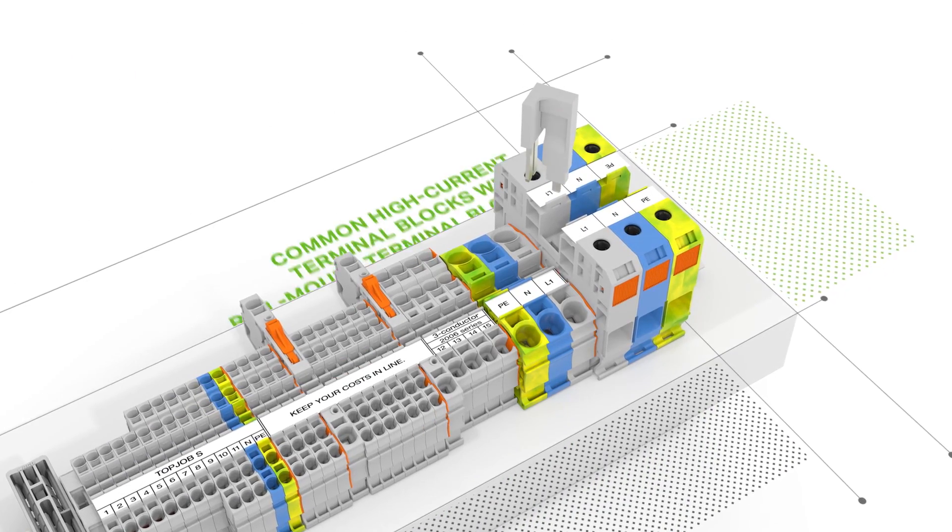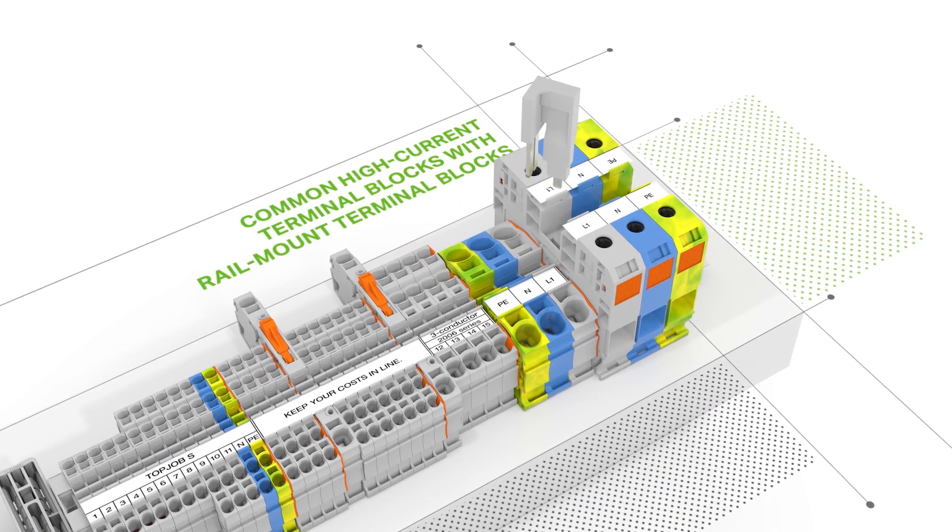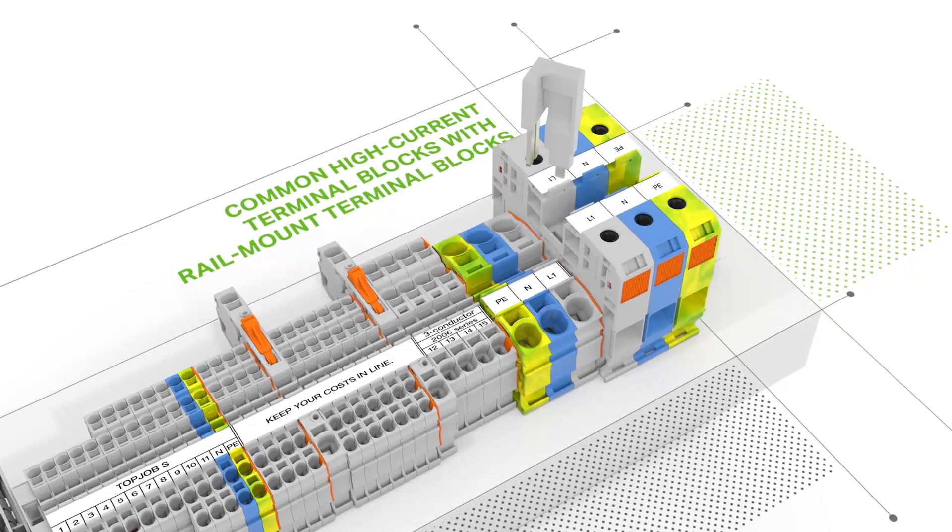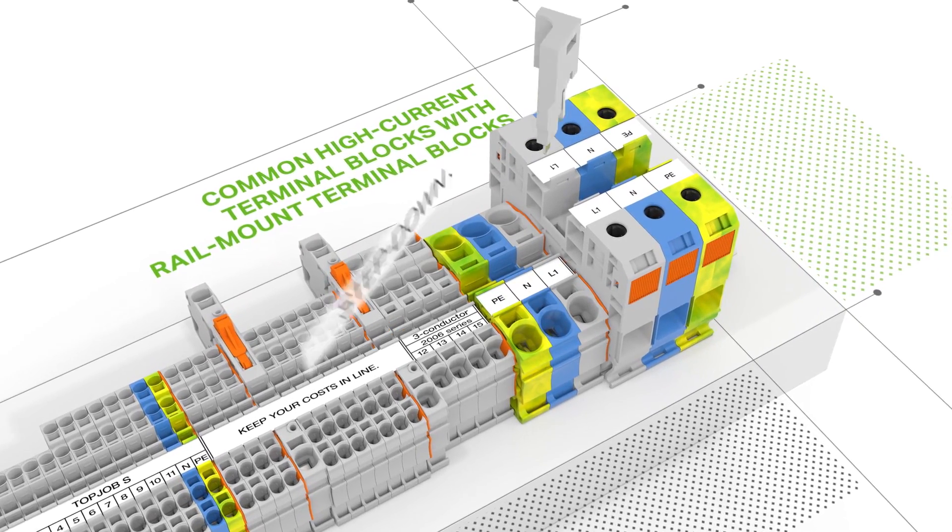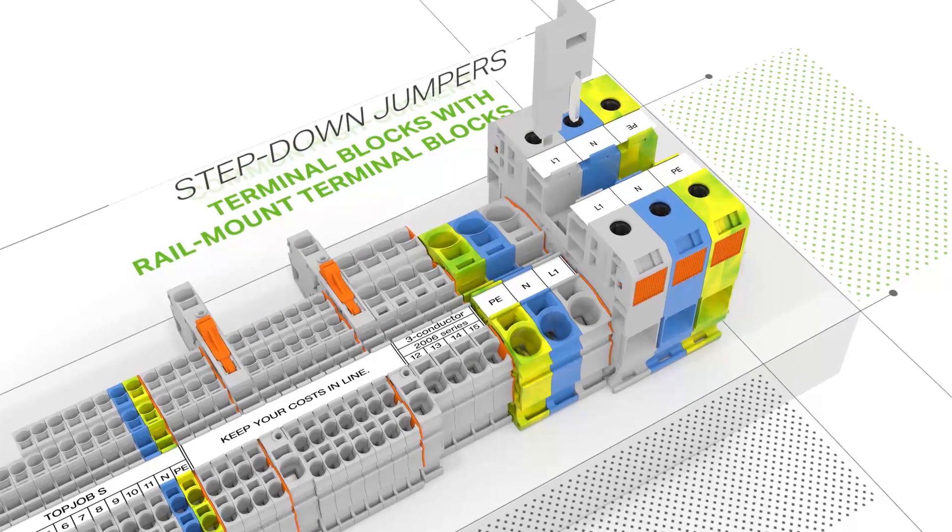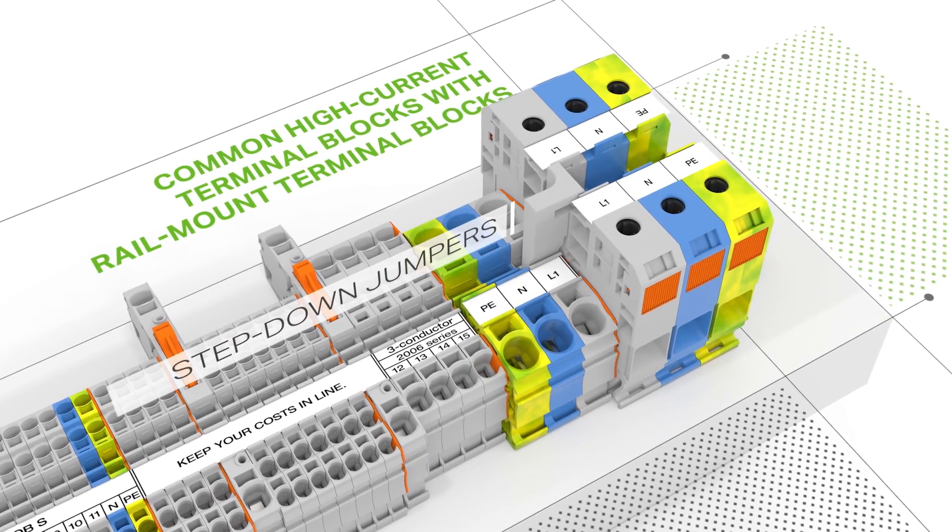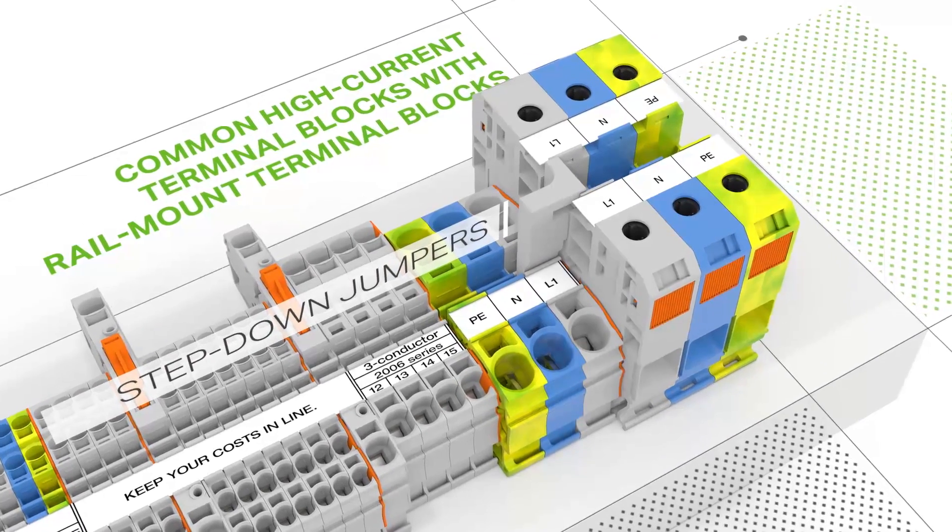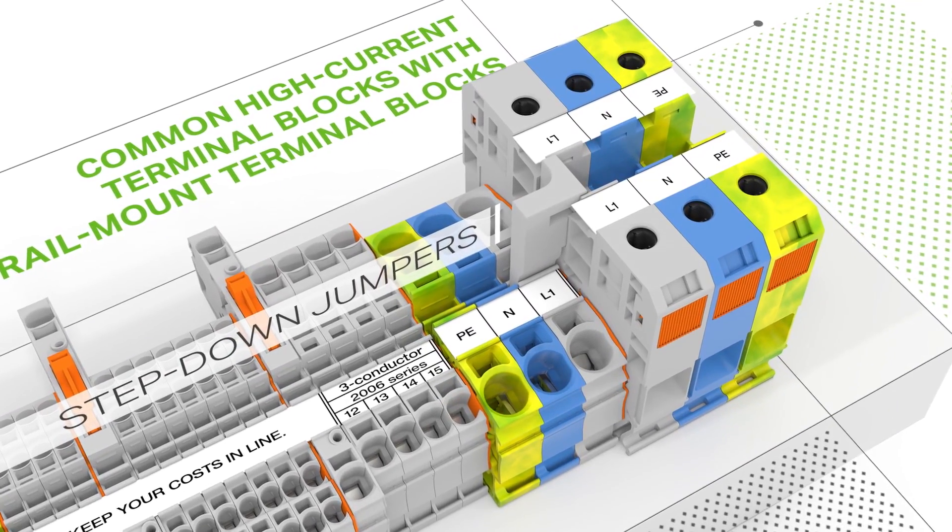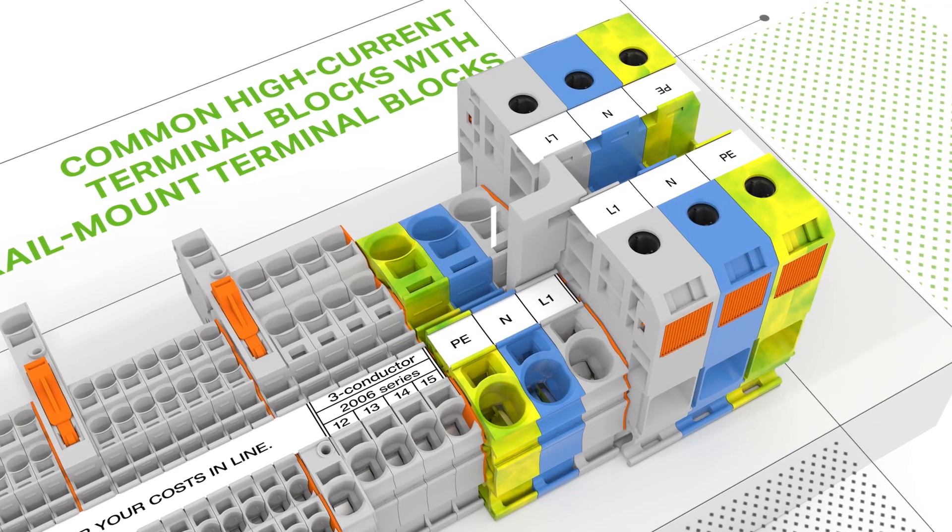Step-down jumpers easily common terminal blocks rated for different conductor sizes. For example, this jumper allows a 35-square-millimeter power cage clamp terminal block to be stepped down to a 16- or 10-square-millimeter TopJob S rail mount terminal block.